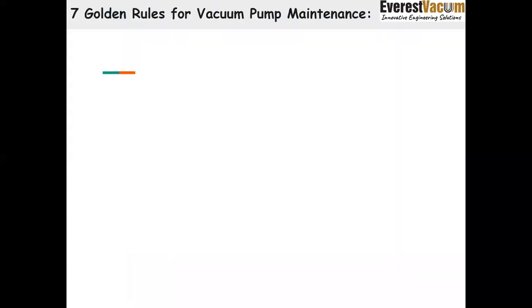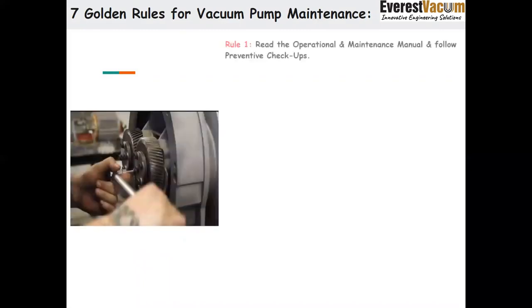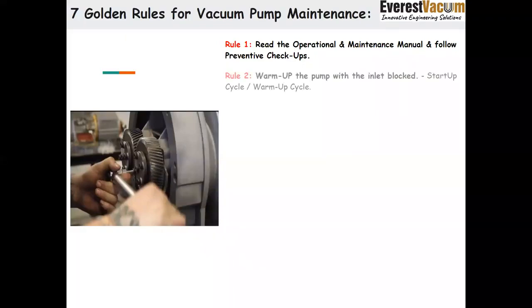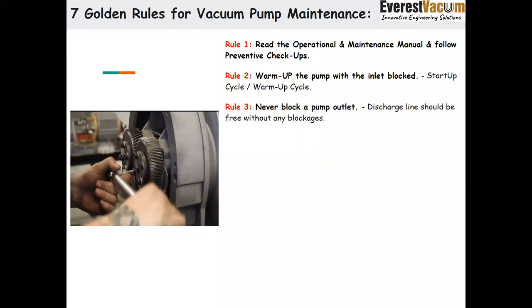So there are 7 golden rules for vacuum pump maintenance. Number 1 is very basic: we need to go through the operation and maintenance manual and follow preventive checkups. Rule 2 is to warm up the pump with the inlet blocked. That is already covered in the previous slides: we need to ensure that the pump gets to its optimum temperature prior to its connection with the client's process. And third is never block a pump outlet. It should be free from any blockages, because if there is back pressure, it can damage the pump.